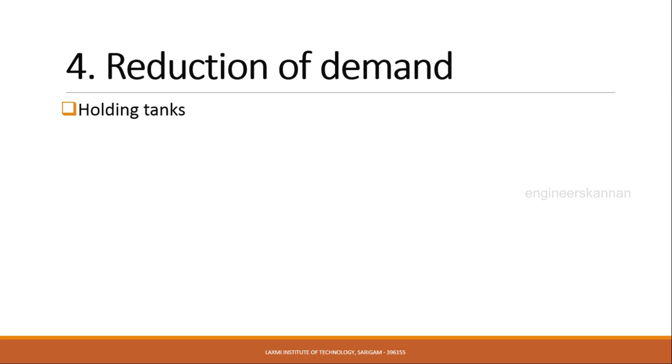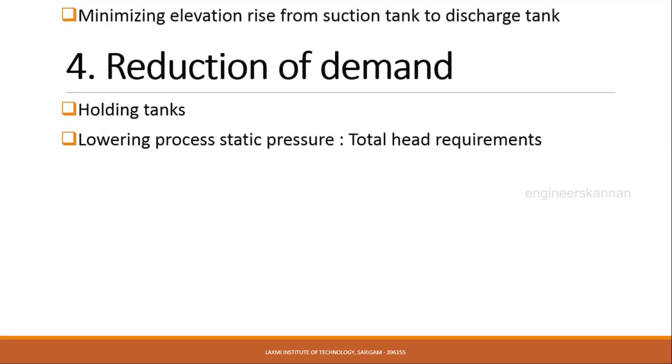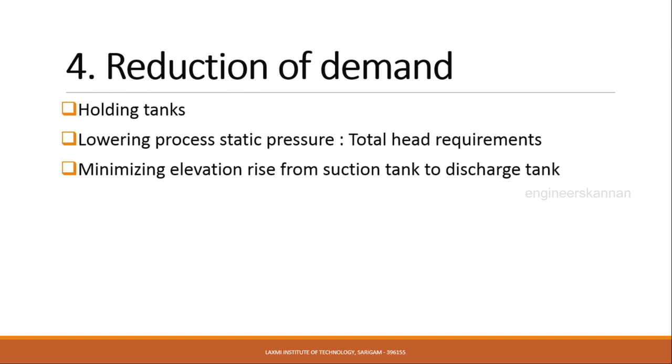Next is reduction of demand. With the help of holding tanks, we can equalize the flow over the production cycle. We can enhance the energy efficiency and pump capacity can be reduced further. The total head requirements can be reduced by lowering the process static pressure and minimizing the elevation level from the suction tank to discharge tank.